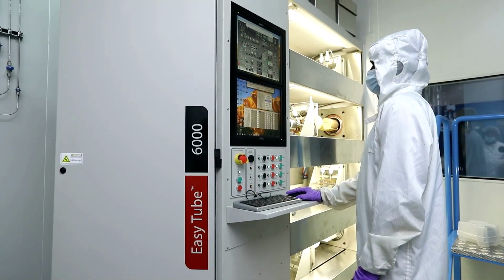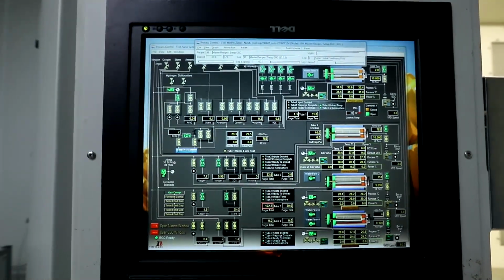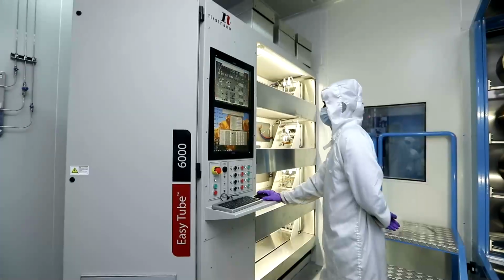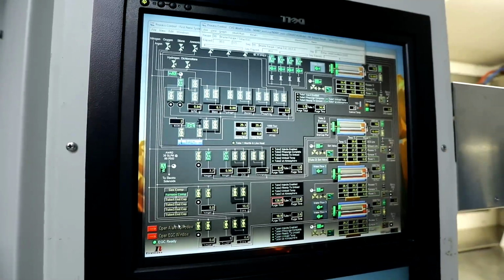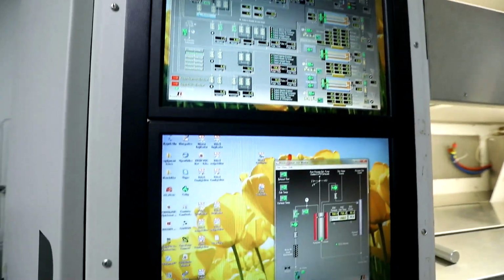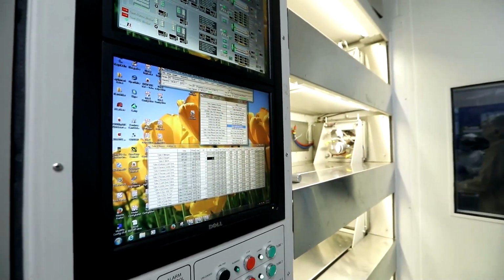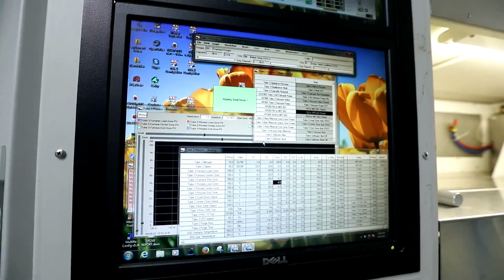After unloading and closing the chamber, remaining toxic gases should be evacuated from the chamber and the gas lines. Next, switch off the EGC unit once the heater temperature is lower than 100 degrees Celsius. During the cooling, nitrogen flow needs to be continued.